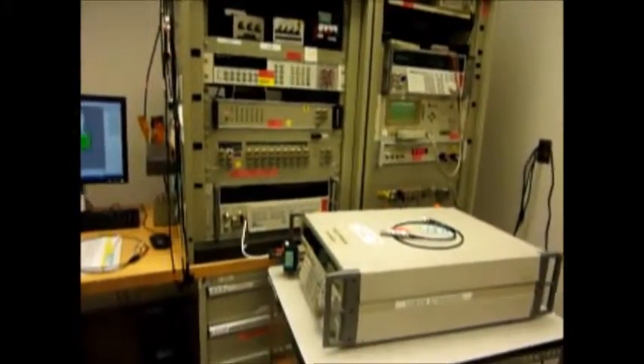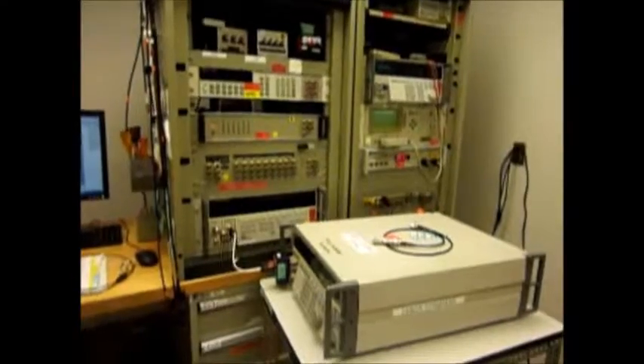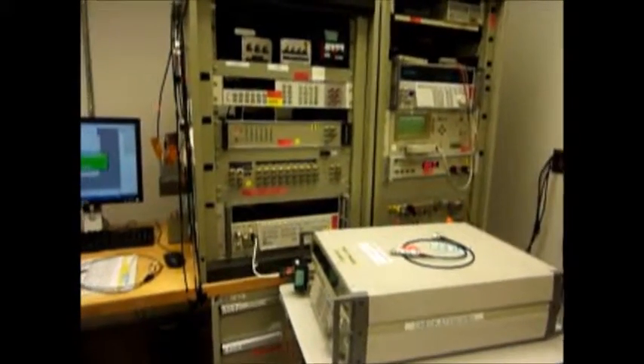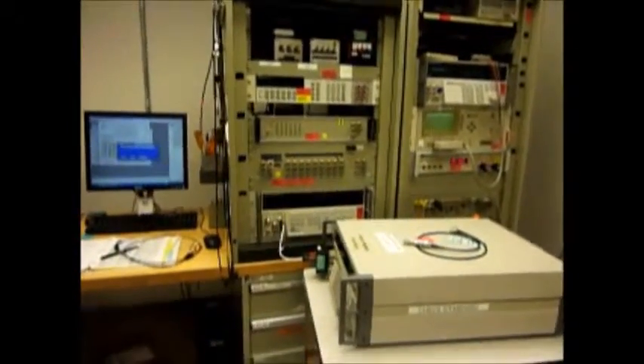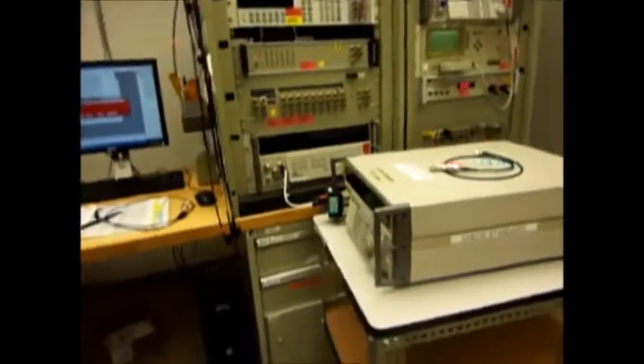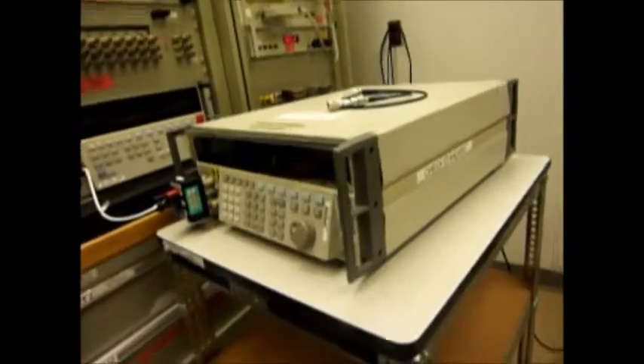This station is specially characterized with individual test and measurement equipment that is characterized in hundreds of test points and used in the calibration of devices like our 5720 calibrator.